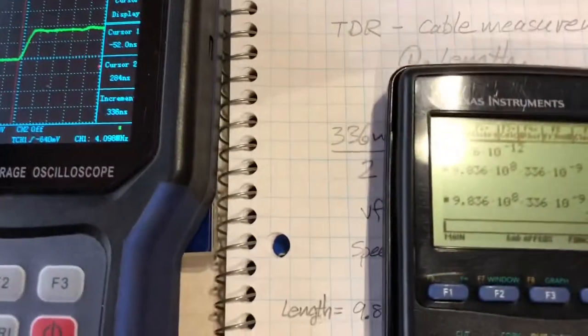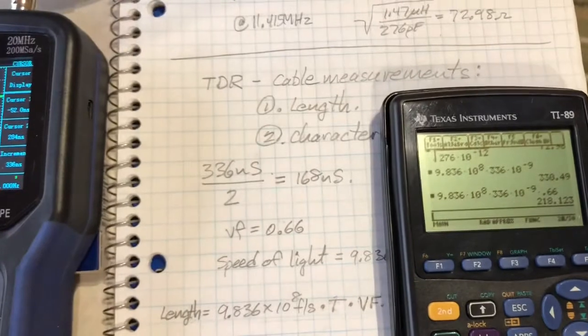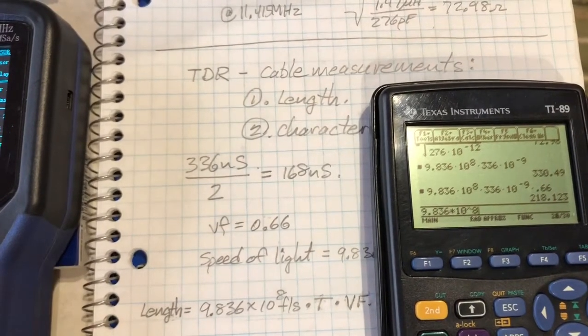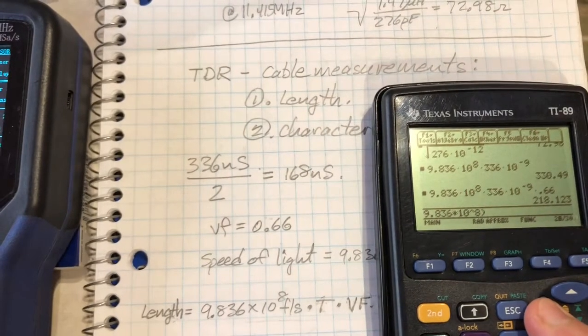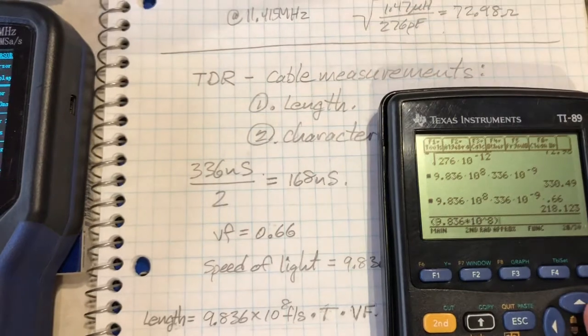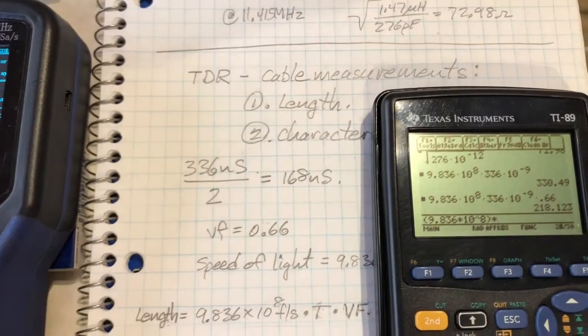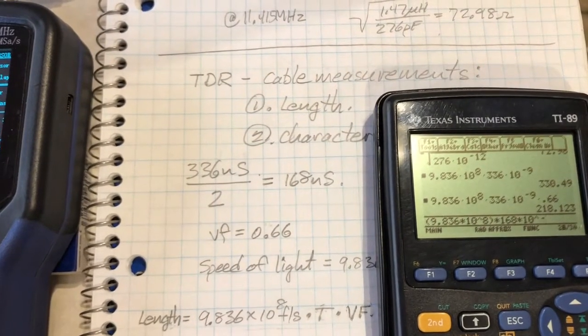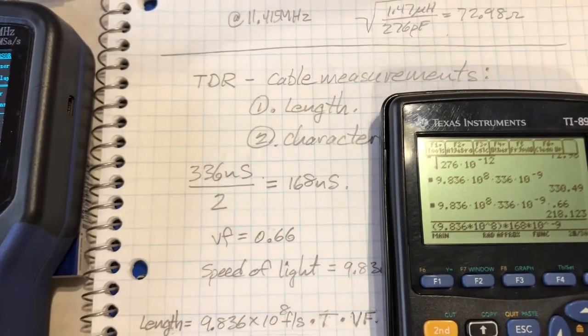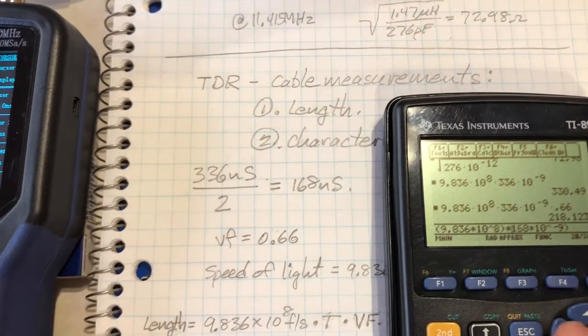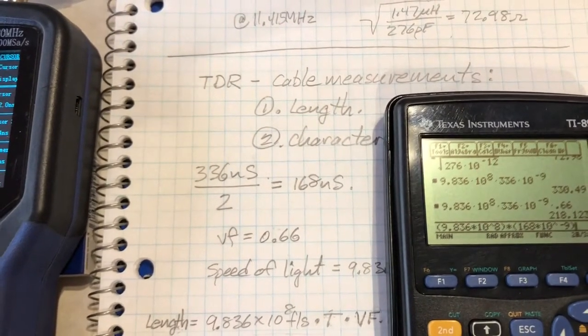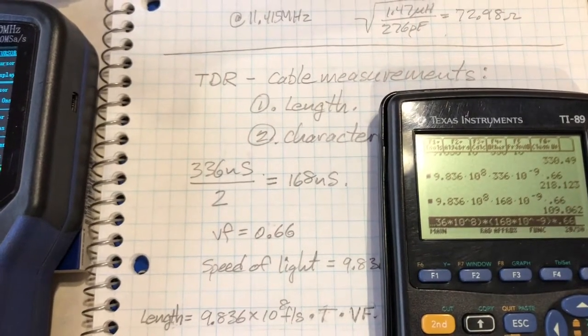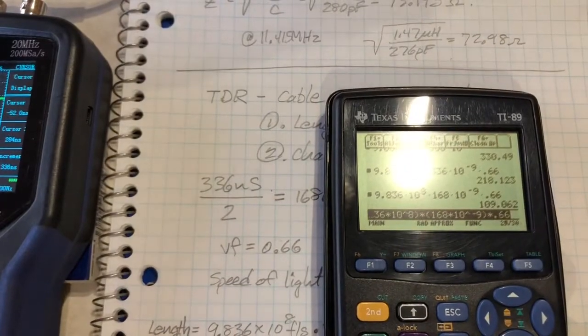Let's plug those numbers into the calculator. We've got 9.836 times 10 to the eighth, and we're going to put brackets around that to isolate it. Now we're going to add the time which we calculated was 168 nanoseconds, so that would be times 10 to the negative 9. We're going to put those in brackets as well. Now we're going to multiply by the velocity factor of 0.66, and when we do that we come up with a cable length of 109 feet.